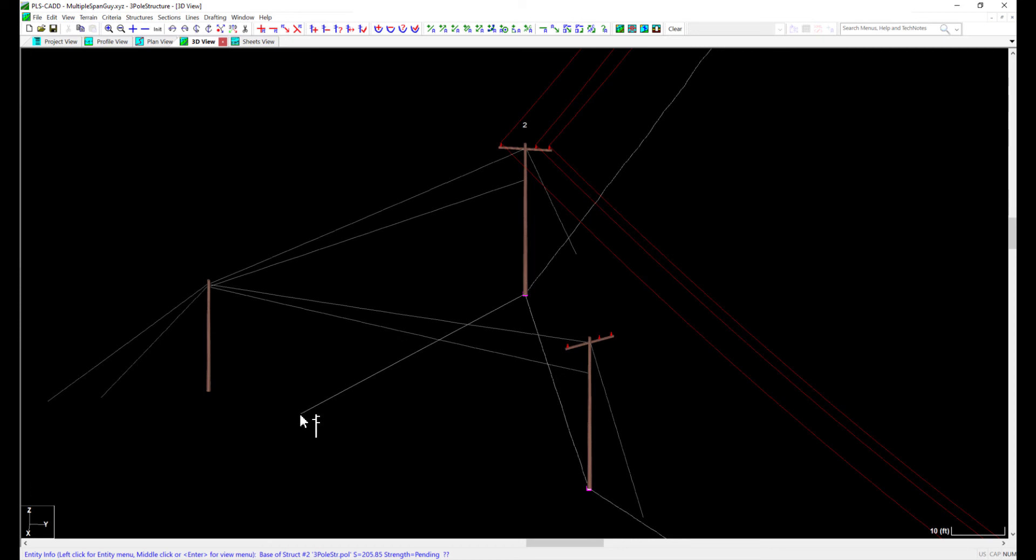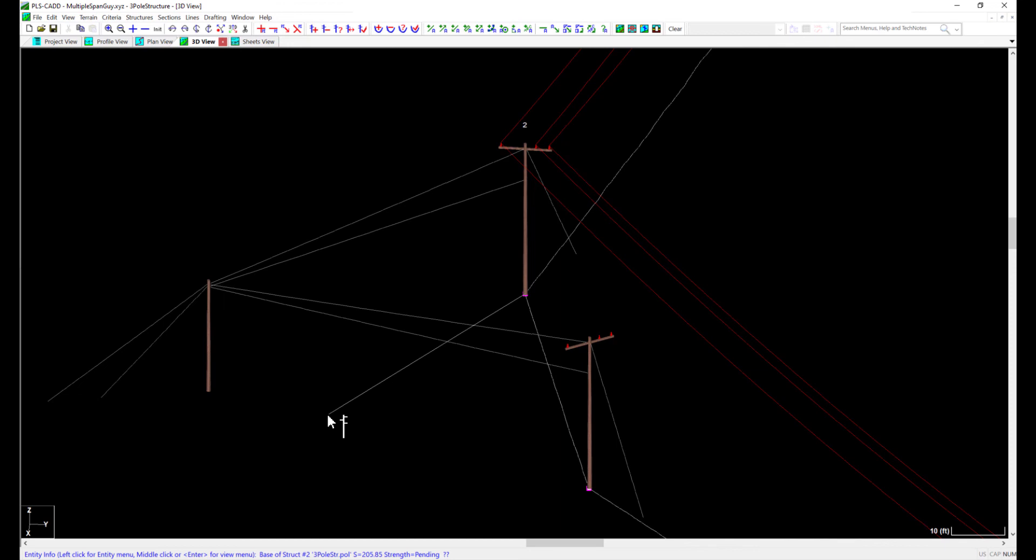This is best done with three individual pole models. Instead of using span guys in PLS Pole for both structures, we are going to use steel conductor in PLS CAD to connect the single poles to the stub pole. This will require a few adjustments to these models, as we will need to set the model up for conductors to be strung where the span guys currently are.